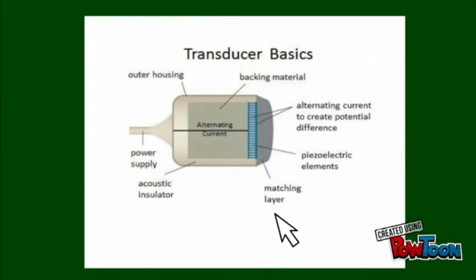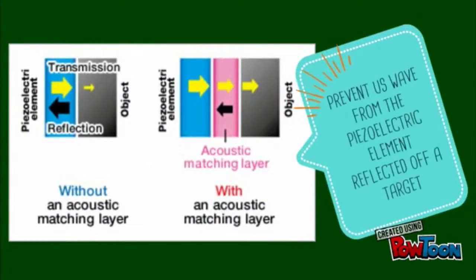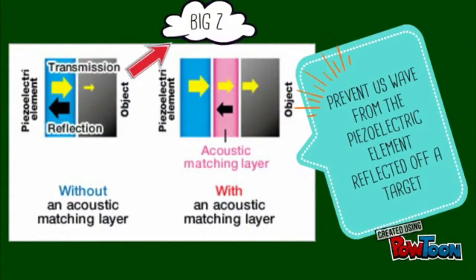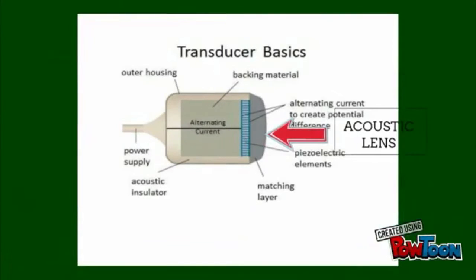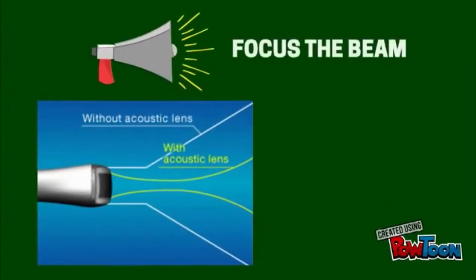The matching layer prevents the ultrasound wave from the piezoelectric element from being reflected off a target due to large acoustic impedance. And the acoustic lens, which is used to focus the beam.